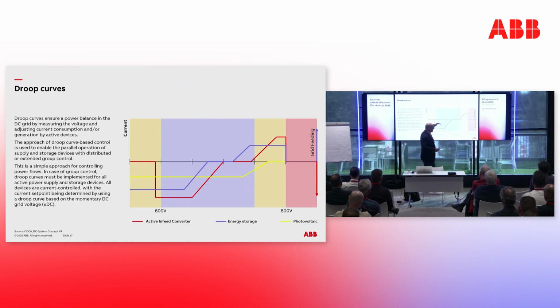This resistance gives us how much current our converter is supplying at a given voltage. For example, the PV is quite flat. Only when we reach over voltage levels do we reduce the power, essentially shedding the power supplied. But for the battery energy storage, we support the system as much as we can. When the system voltage becomes too high, we start charging the battery back. With the in-feed, we always use it, and use it fully, and with the in-feed we also start charging back to the grid when that's possible. In this way, we can coordinate the sources between each other without having a communication link.